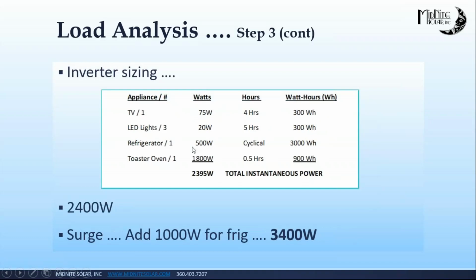While we're here, another aspect to derive is the size of the inverter needed. There'll be another webinar series on inverter sizing, but briefly: even though we added up 4,500 watt hours of total energy stored and consumed through these appliances, at one moment in time I need about 2,400 watts of total instantaneous power. The toaster oven, for example, only consumes 900 watt hours total, but at the moment it's operating it actually draws 1,800 watts. So the inverter needs to support that. We have two different values here.